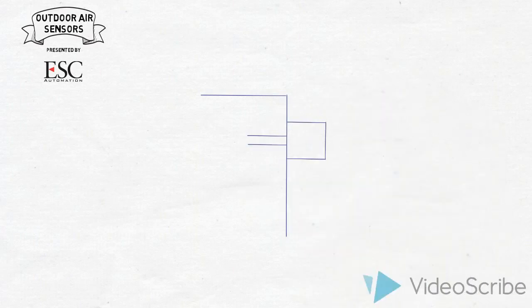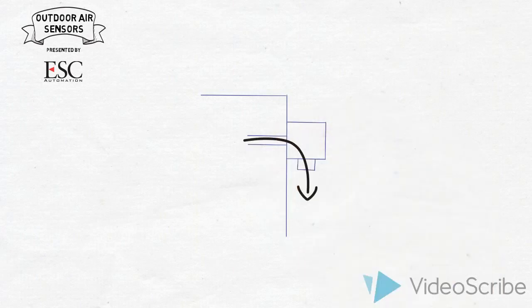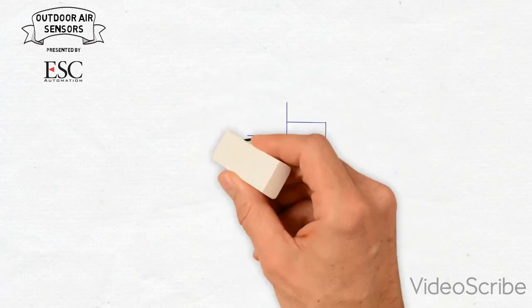We mount the box on the wall and we have our sensor, and sometimes if this pipe, if the building is over-pressurized, we'll actually get air circulating out of the pipe that affects your outdoor air sensor. So you want to make sure that we silicon the pipe that leads to the outside of the building. We don't want to have any outside air affecting the outdoor temperature sensor. That's probably one of the most important rules.